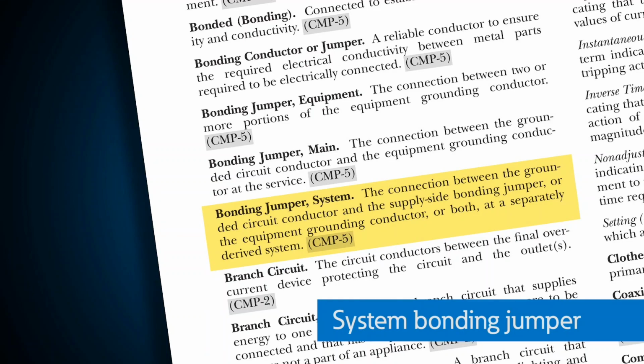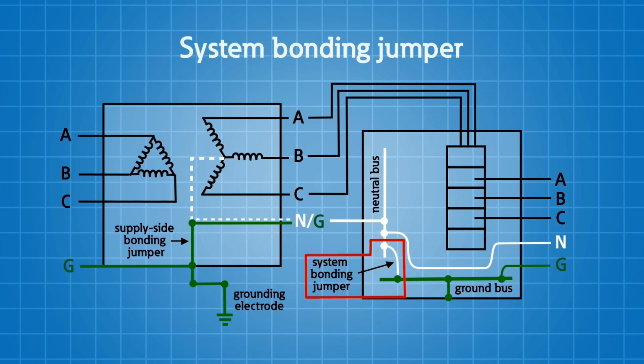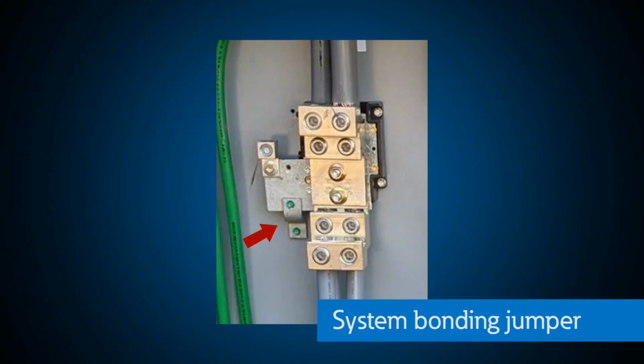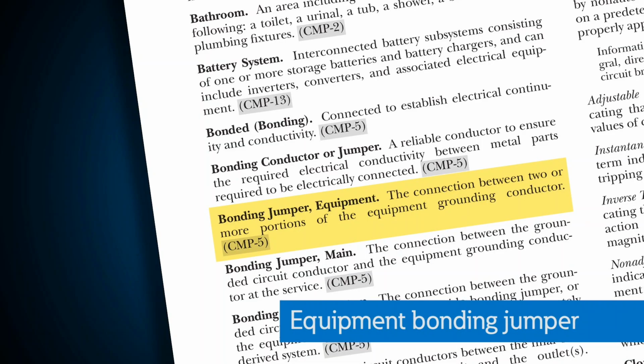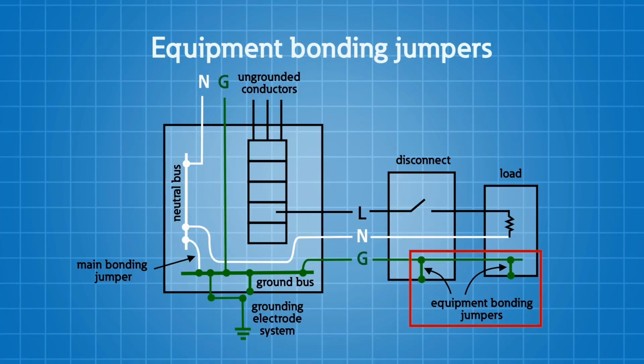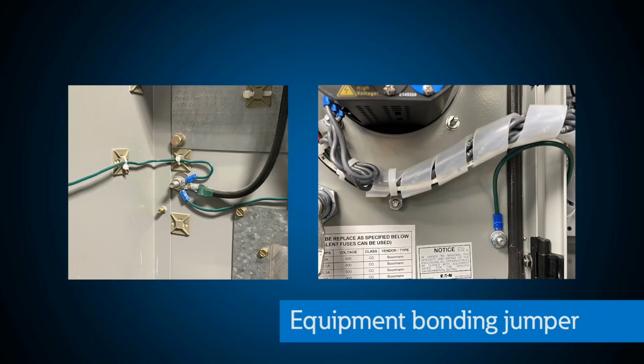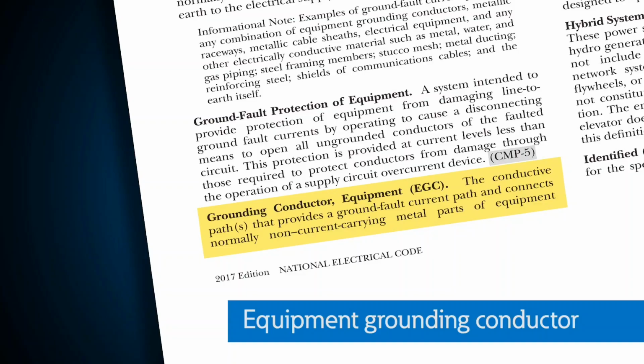All right, so let's talk about the system bonding jumper. This is the connection between the grounded circuit conductor and the supply side bonding jumper. We have a system ground where we're establishing our ground, and we need to bond those two together, and that's what this is all about. Your equipment bonding jumpers are the connections between two or more portions of the equipment grounding conductors. We have to make sure that we bond everything together, and anytime we put jumpers between your equipment grounding conductor and any of the steel that needs to be bonded, those are your bonding jumpers.